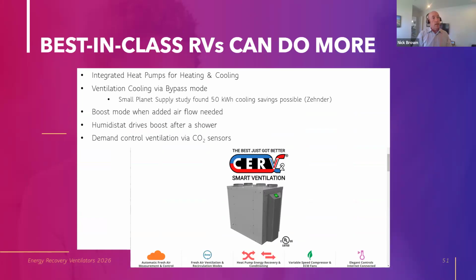But some have integrated heat pumps, for low load dwelling units and multifamily ADUs. This one box can do heating, cooling, and ventilation. Others are able to do ventilation cooling, like a whole house fan that Chris Rosemont asked about earlier, by bypassing the core when the outdoor air is cool enough to be conducive to the indoor space. And we found savings of about 50 kilowatt hours in cooling savings possible using that type of feature.